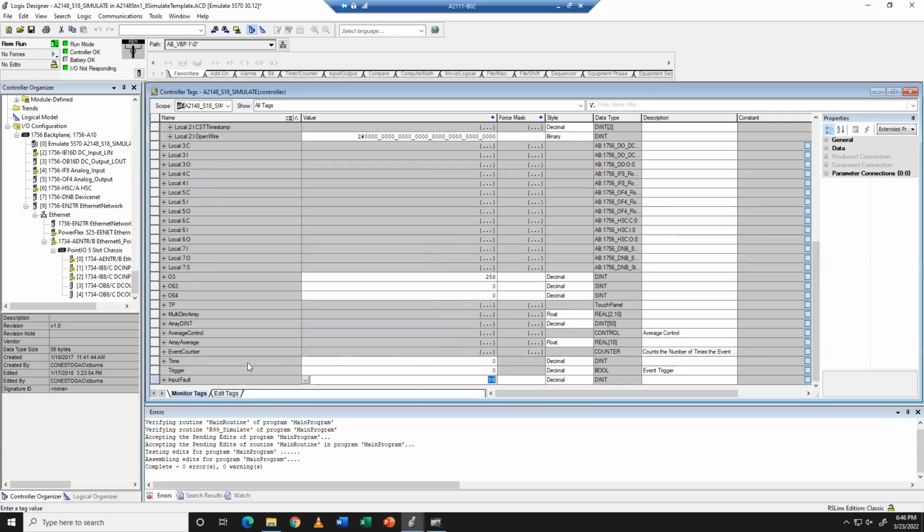So they'll have inside their program a bunch of internal information, and then they'll create an alias for that, and they'll just have like SCADA tags or outbox tags, and they'll move their information into their internal bits. And then for messaging purposes, SCADA only reads the alias. So it doesn't matter what they move into them, they could populate them and they're called a specific thing. And they don't have to worry too much about moving data around.